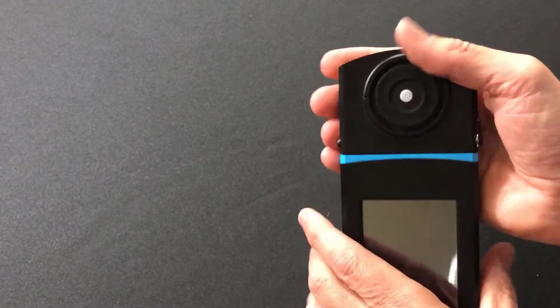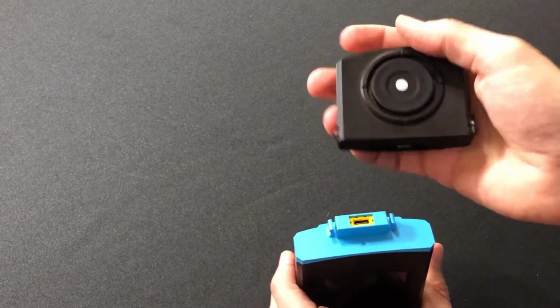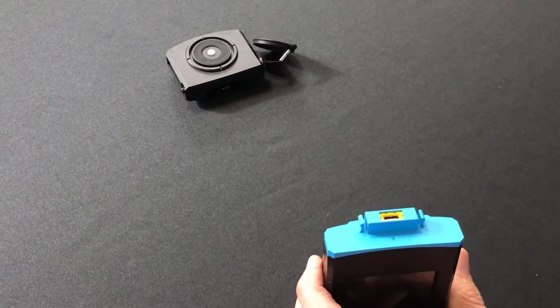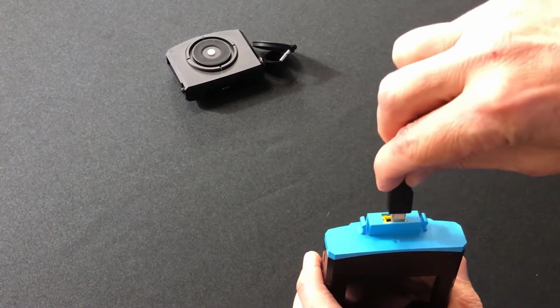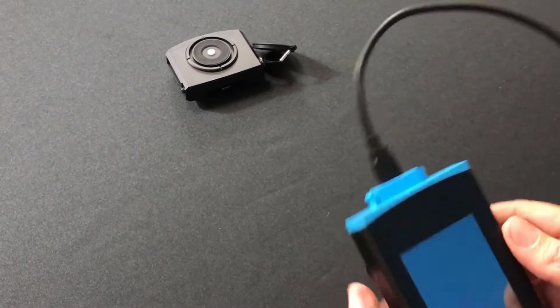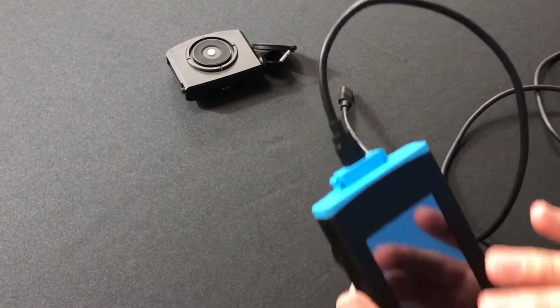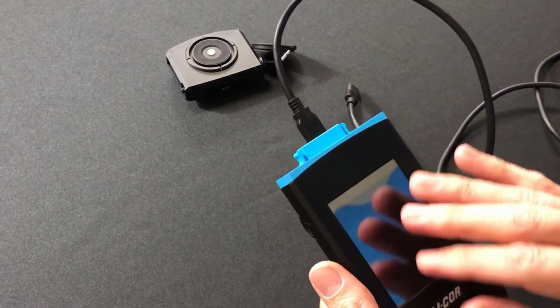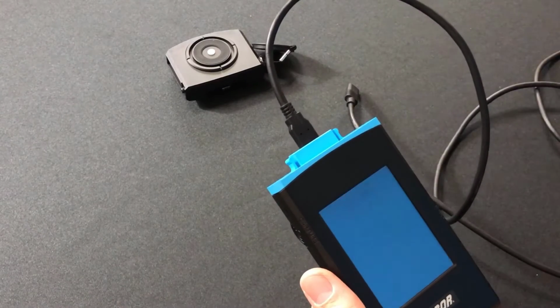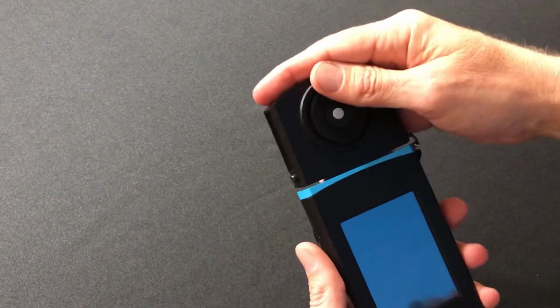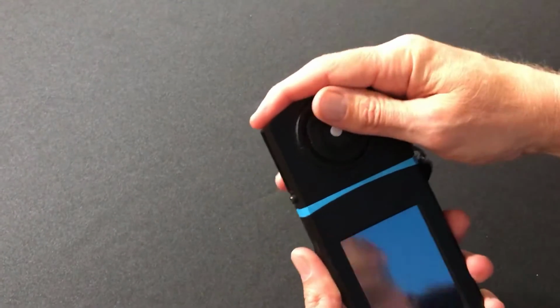Now, the other thing I talked about earlier is that you can take apart the console and the head, and let's say we want to make measurements off at a distance. Then we use this extension cable and we can insert that into the port here. The other end connects to the head. And what we can then do is make measurements and control the device and see the data coming in real time, even though the sensor head is located in a different location. And we can just put the two back together as such.